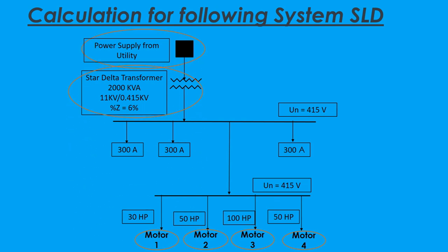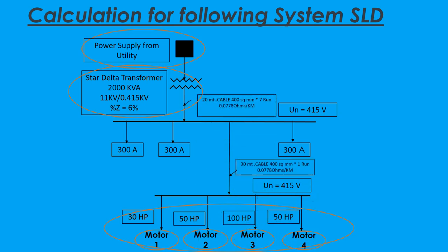This system consists of a source of 11 kV and a transformer of 11 kV by 0.415 kV. The system consists of four numbers of motors connected as load, operating at 415 V. For power transmission, seven runs of 20 m 400 sq. mm cable and one run of 30 m 400 sq. mm cable are used. We will calculate fault current for Point No.1, Point No.2, and Point No.3.